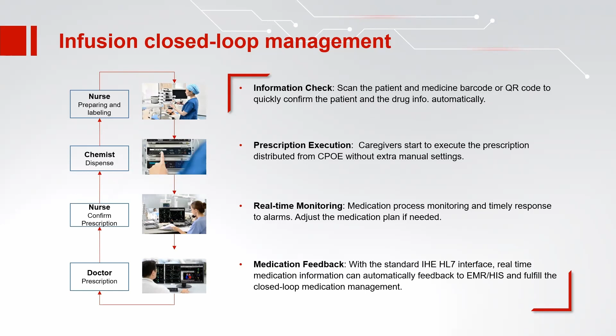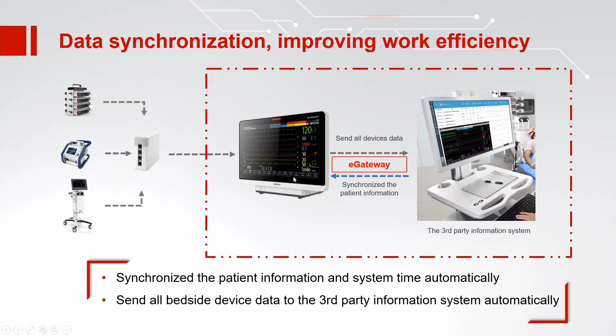And for the data synchronization to the hospital systems, we can use the e-gateway software. We know nowadays in hospitals there are a lot of different HIS systems from different suppliers, but they're all using the standard HL7 communication protocol. So with e-gateway functions, we can achieve communication between the patient monitors and central station systems and your hospital systems. It can synchronize the patient information and the system time automatically, and send all the bedside device data to the third-party information system automatically. And also, if the patient is already registered in the systems, it can synchronize to the patient monitors in the ICU. So this data synchronization can highly improve the working efficiency.